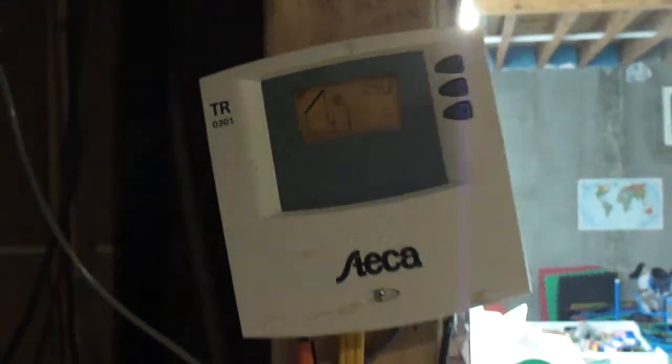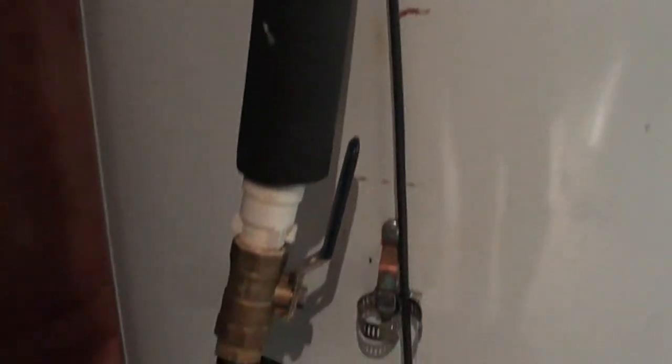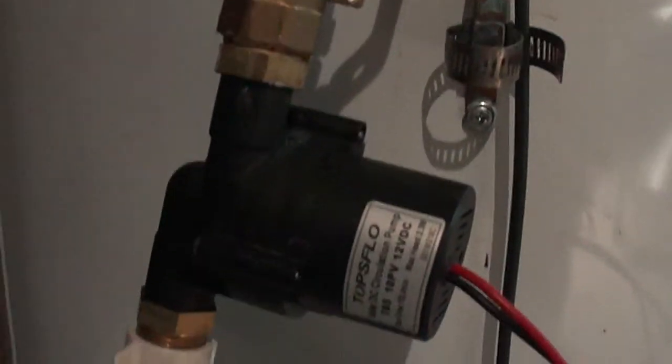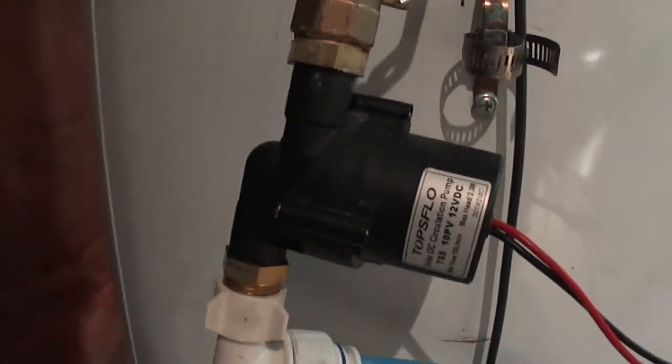Right now the bottom of the tank is 139°F and the collector is at 150°F, so we had a nice sunny day. It's getting to be 2:30 in the afternoon and you can hear it's still running. We've got a 9-watt pump from TOPSFLO — you can probably hear it.